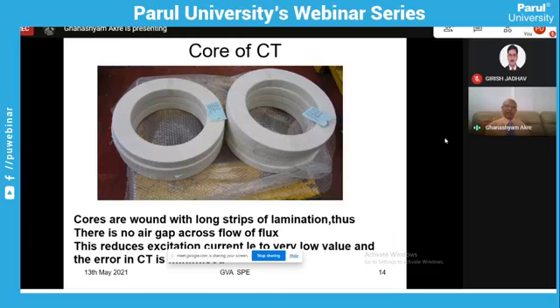If you use rectangular type cores, which have air gaps, then it will draw a very high magnetizing current, and that will produce very high values of errors, which is not required. Hence, particularly for our current transformers, the magnetic circuit must have a gapless system. That means it should not have any gap. And that is why these toroids are made out of a long strip of CRGO, and they are wound, annealed, processed, and then presented.